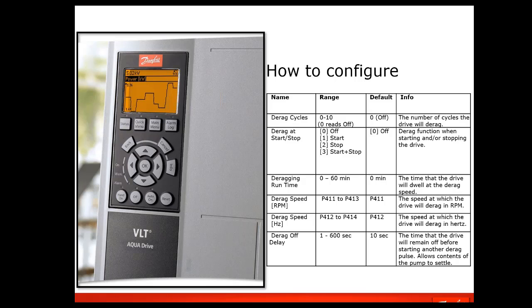Configuring the deragging feature is pretty simple. The parameters in the drive for that feature include the number of cycles, if you want it to be triggered based on the start stop. Let me get a pointer here. There we go. Like I said, the cycles could be 1 to 10 times. This setup actually turns the feature on as the main on-off for enabling the feature. By default it is off, but you set it for how many cycles you want it to run. And again, you can have the feature as a preventative function every time the drive will start or every time it will stop, or both.